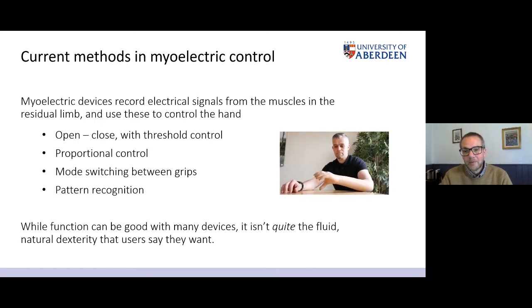If we look at the current methods for control in myoelectric devices, what happens is that there's an electrical contact between the socket and the residual limb of the user, so an electrode makes contact with the skin. As the user then contracts the muscles in their residual limb, those muscles produce an electrical signal, and that's picked up by the electrode, and then converted into a signal sent to the motors in the myoelectric device, that tells that artificial hand to open and close or do some other function. So that's the means of control. And it might be as simple as opening and closing. So contract the muscle on the back of the arm, the hand opens. The muscle on the front of the arm, the hand closes. It could be that that's proportional, so the harder you contract that muscle, the faster the device moves.